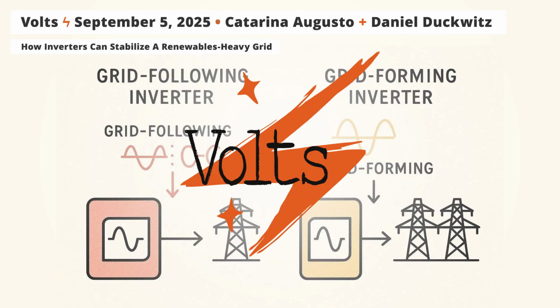So turning on the stove is probably not the reference scenario for planning the security of supply of a larger interconnection, but instead it would be scenarios like a sudden loss of a really large generator, like a gigawatt scale power plant, or like a transmission failure that suddenly disconnects a really, really large load center. And in these cases, it's not, sorry to say, as insignificant as your stove to the power system. It is really getting the system into trouble. What happens if there is such a sudden unbalance is that this instantly missing power will be taken from the rotational masses, from the energy of these flywheels in the synchronous generators.